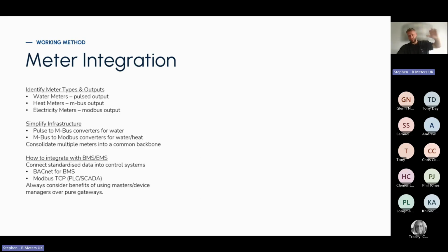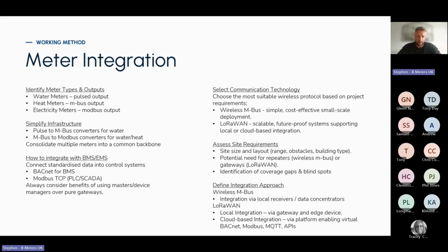Meter integration, wired and wireless. Identify the types of outputs - for water meters, you might have pulse ports. Simplify the infrastructure: pulse to M-bus converters for water, and then M-bus to Modbus converters for water and heat, consolidating multiple meters into a common backbone. And then how are you integrating that with the BMS or EMS?